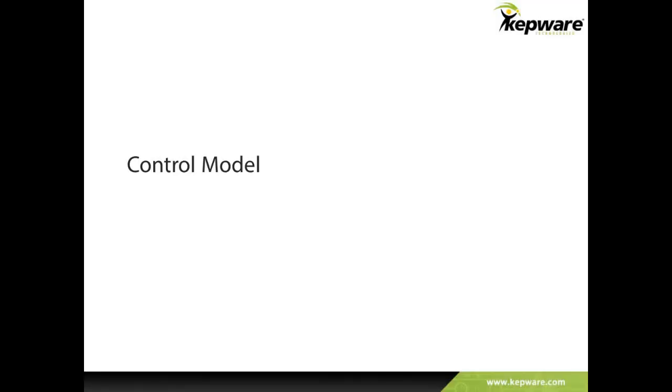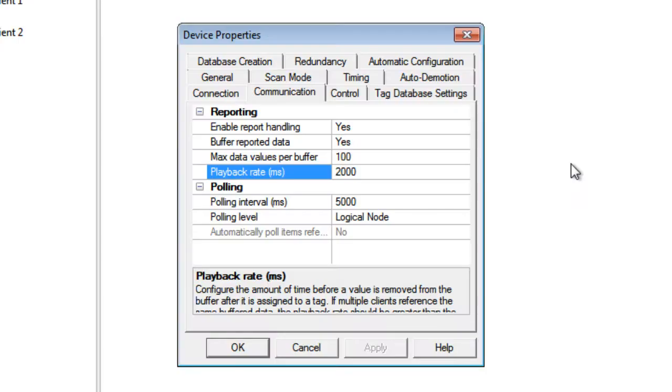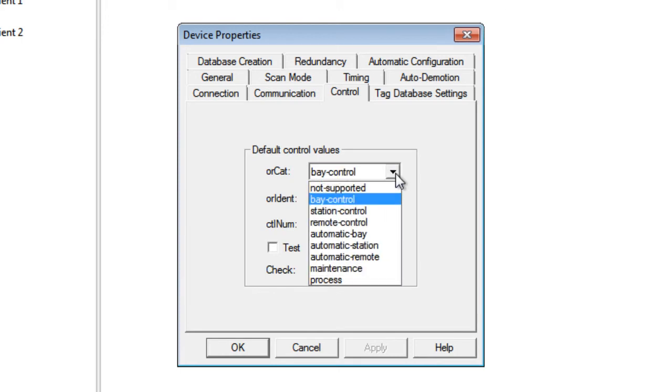The last feature we will cover on the IEC61850 MMS client driver is the ability to specify a control model for a device. In order to control the function of an object such as turn a switch on or off, users must write to a group of tags at once. These include orcat, orident, control num, test, and check. The IEC61850 MMS client driver makes this process easier by implementing a control model setting for the device.